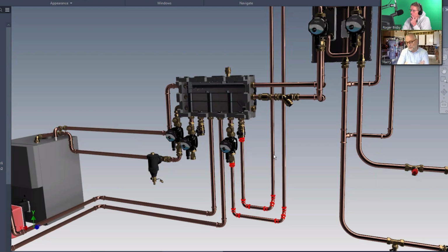There's another major benefit. If you understand the principles of that job, you understand how we do a hotel, how we do a commercial factory - for example, a very well-known soft drinks company, I won't say the name, had two air compressors dumping the heat and having problems. So we took the air compressors, put them into one connection on the manifold, connected their existing boiler into the other side, and now they're heating all their offices with their air compressors. It's incredible the number of times you see people just dumping heat from industrial processes, and you walk past and feel this heat blowing out from somewhere.